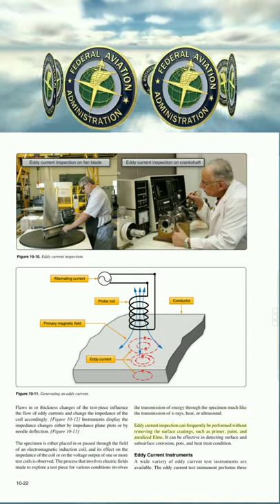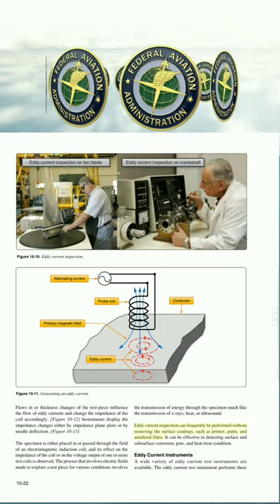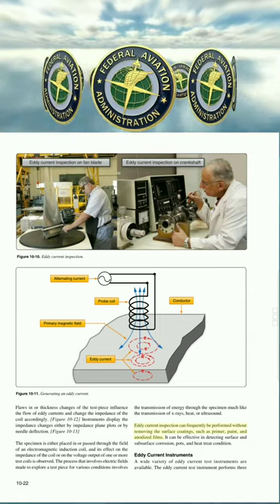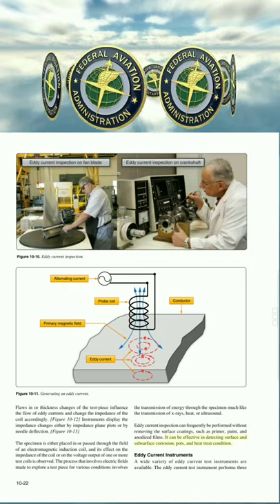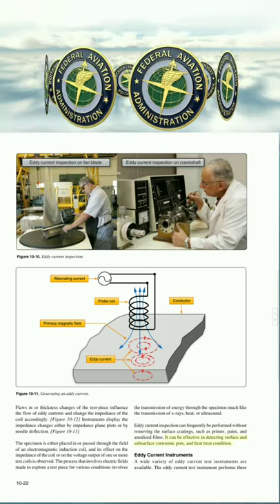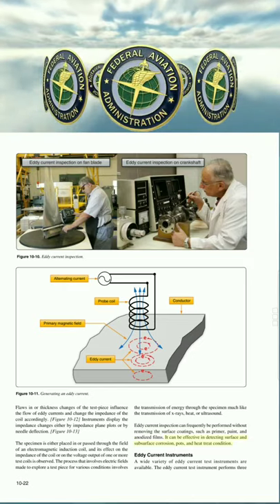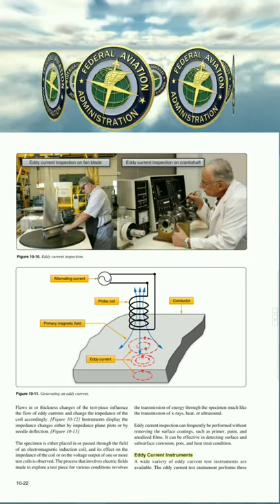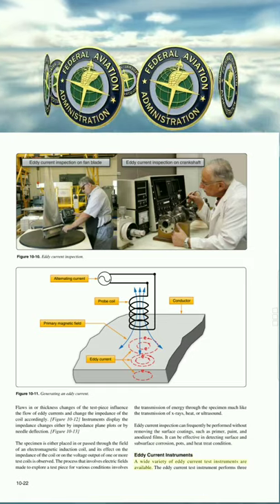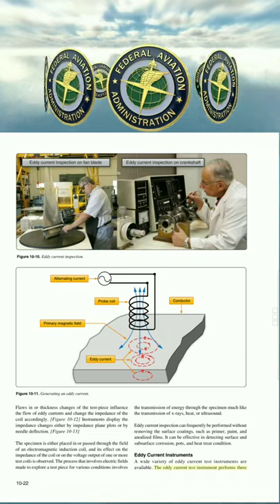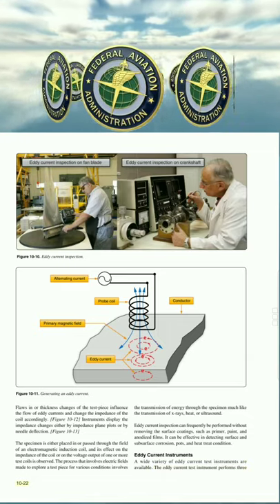Eddy current inspection can frequently be performed without removing the surface coatings, such as primer, paint, and anodized films. It can be effective in detecting surface and subsurface corrosion, cracks, and heat treat condition. Eddy current instruments. A wide variety of eddy current test instruments are available. The eddy current test instrument performs three basic functions.